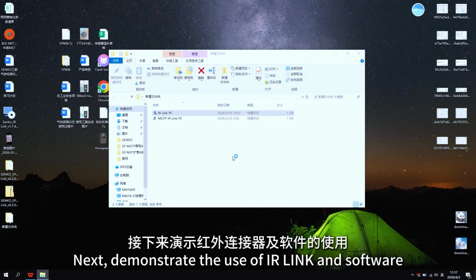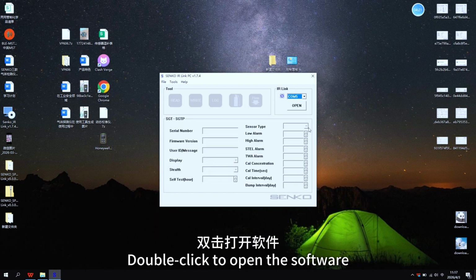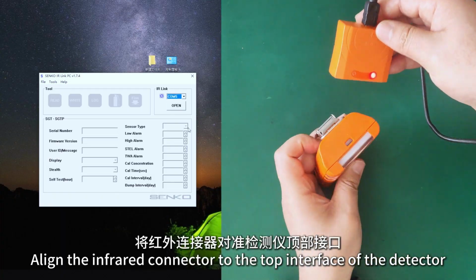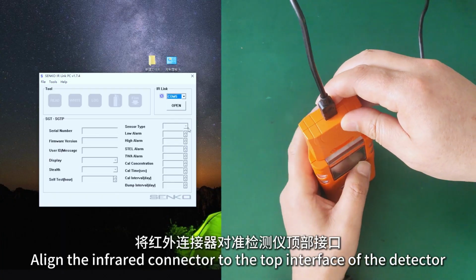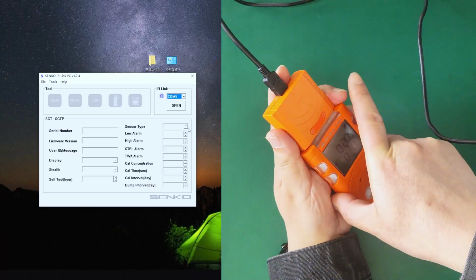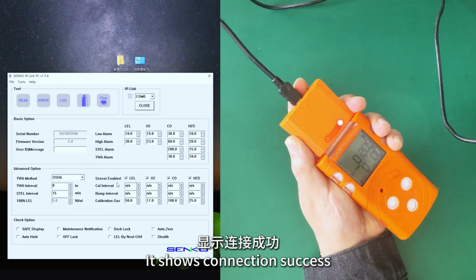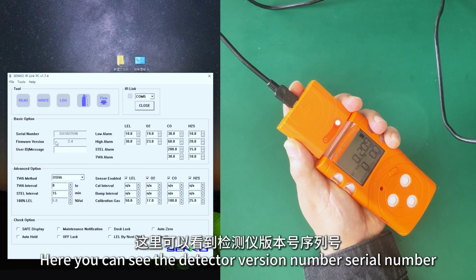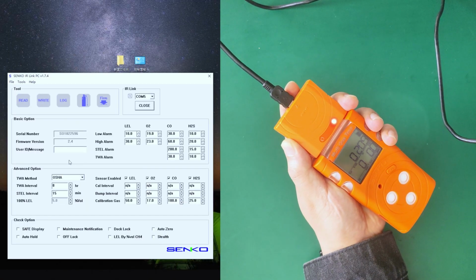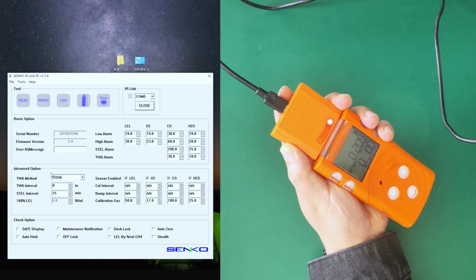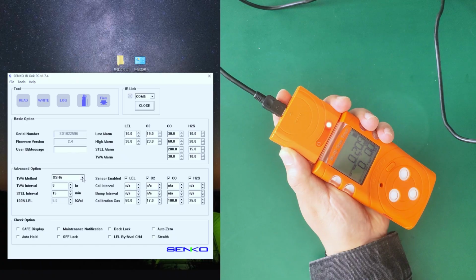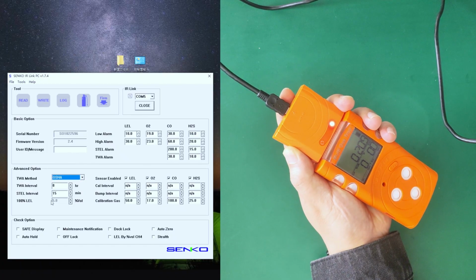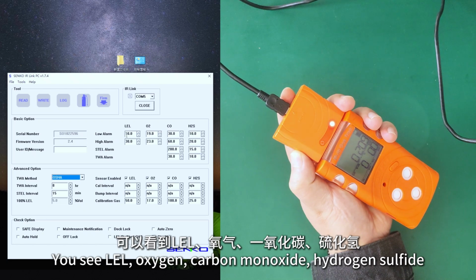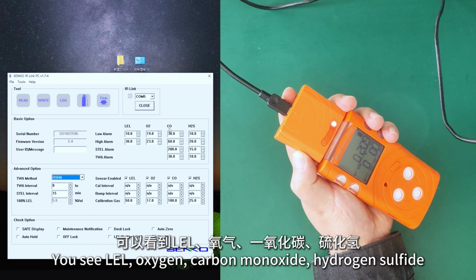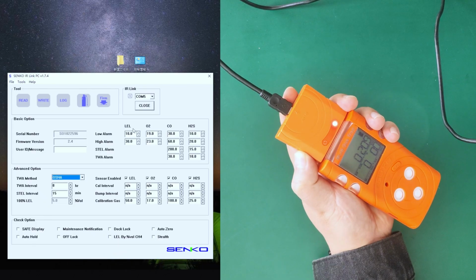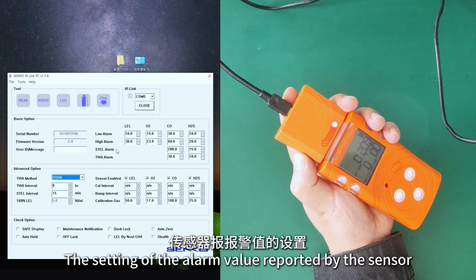Next, demonstrate the use of IR-Link and software. Double-click to open the software. Align the infrared connector to the top interface of the detector. Click Open to connect. It shows connection success. Here you can see the detector version, number, serial number. TWA method. You see LEL, oxygen, carbon monoxide, hydrogen sulfide. The setting of the alarm value reported by the sensor.